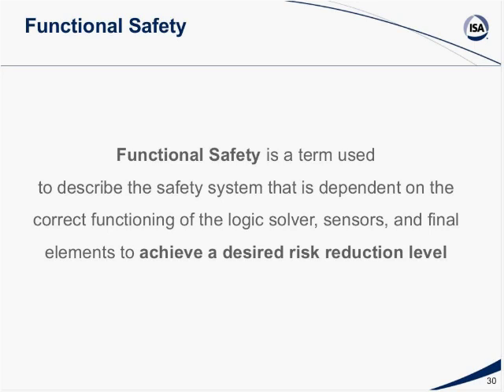During some of these dangerous failures, or the need to control them, industry experts began to address functional safety and formalize an approach for reducing risk in the process plant environment through the development of various standards like the ones that Jerry mentioned, the 61508, 61511 or the ISA 84. Previous safety standards were generally prescriptive in nature and not performance-based, and an emphasis on quantitative risk reduction, life cycle considerations and general practices make these standards different from their predecessors.